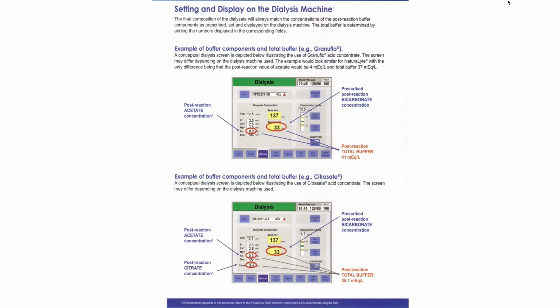And what was occurring in this is that this is actually the value that the sodium bicarbonate load is contributing to patient experience. The problem is that acetate is converted to bicarb. So if you were to set your machine, which is a value that happens before that systemic contribution, and you think that that's what the patient experiences, it really isn't, because you have to add the 8. So the total patient buffer experience of the patient is 41.